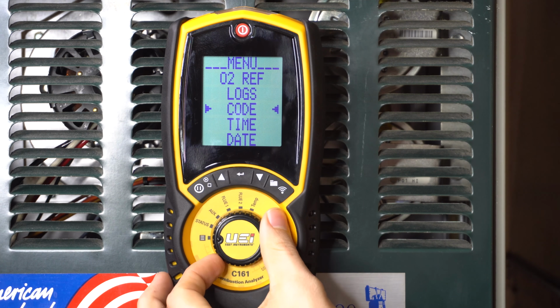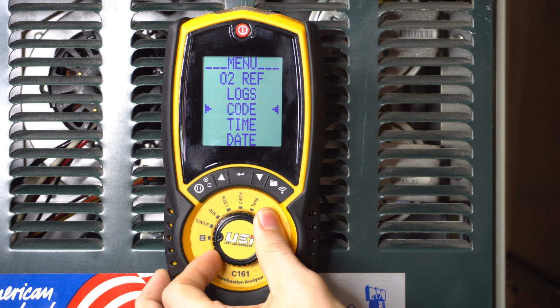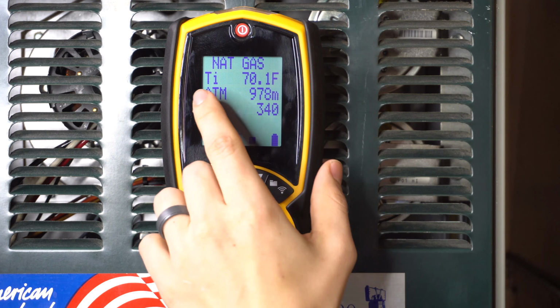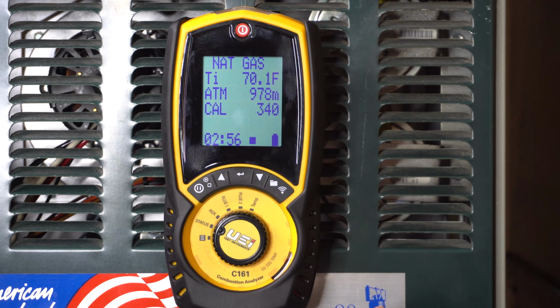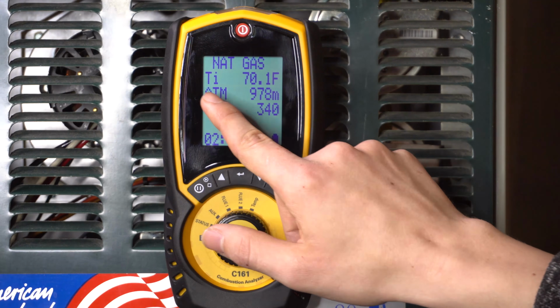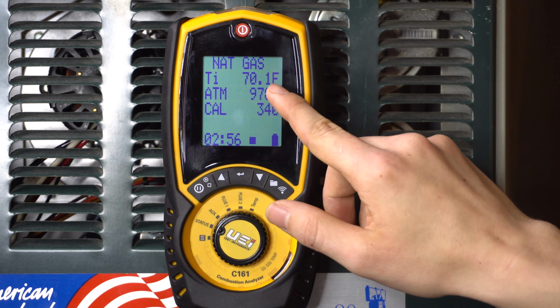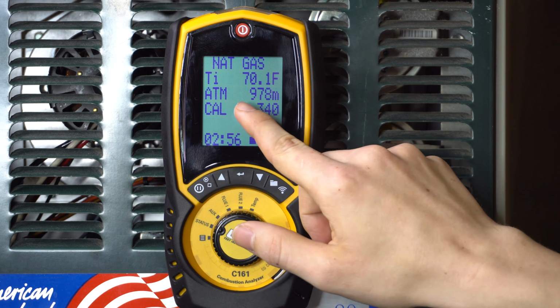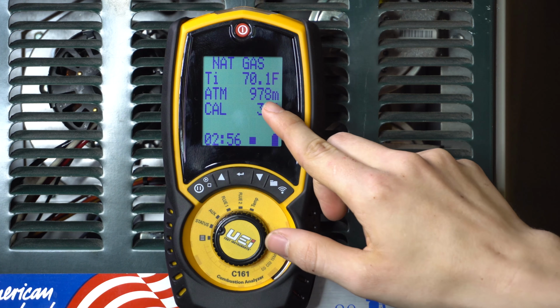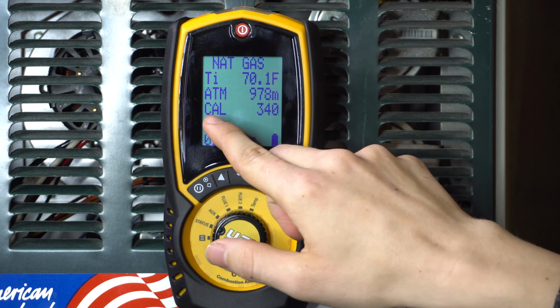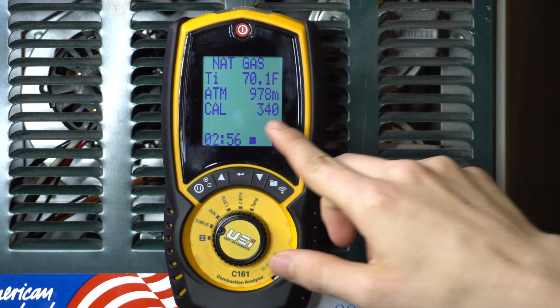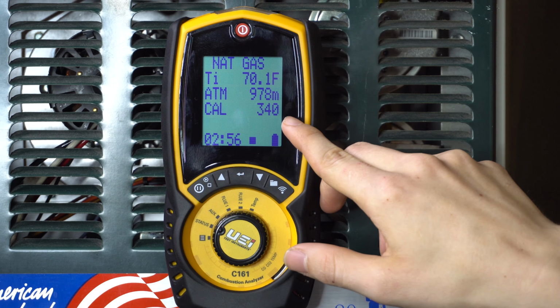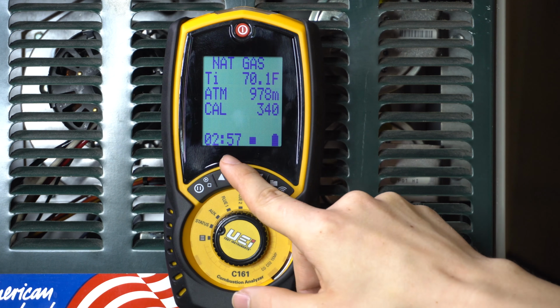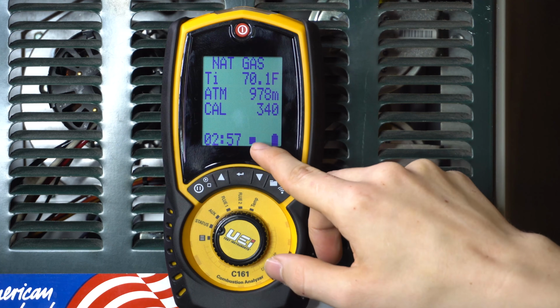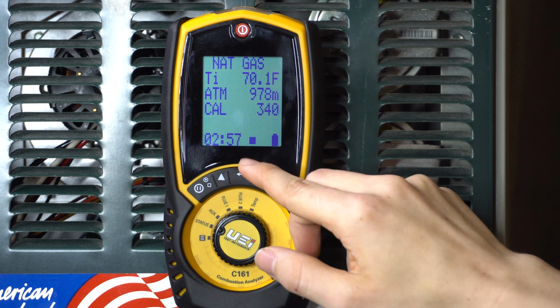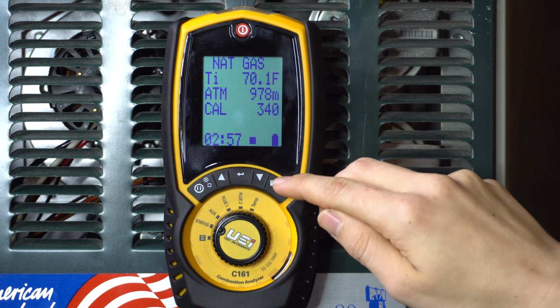And if we go to our next menu, which is the status menu, this menu just shows us that the analyzer is set to natural gas. TI stands for the ambient temperature, so it's 70 degrees in the room right now. ATM is the atmospheric pressure, which is 978 millibars. Cal is just for calibration, that is due in 340 days. There's the clock, it's 2:57 right now. The stop, which just means that the pump is stopped, it's not running, and how much battery life remains.